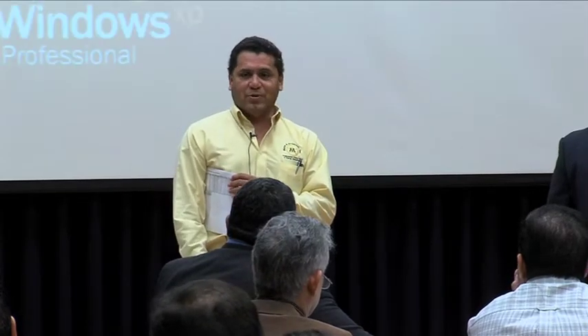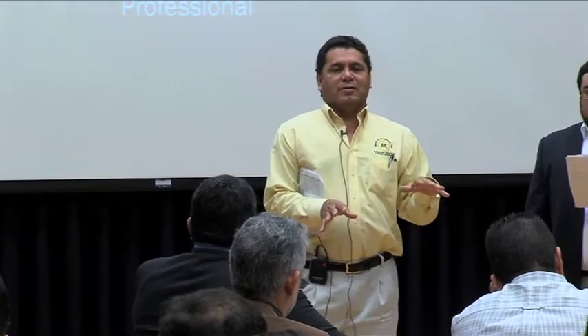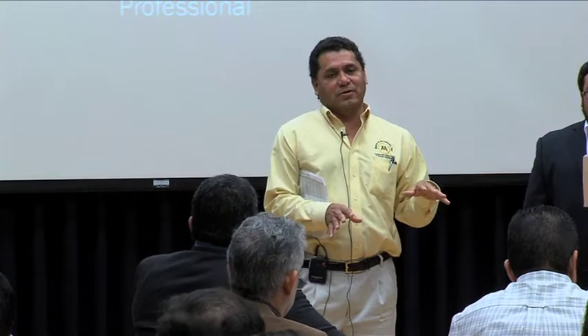There's heat recovery chillers, and if you want to get into that, Perry is the guy to talk to. I did them when I was with AEP. I put a couple of them in a couple of colleges up north, and they can replace 5 million BTU gas boilers. You're just moving the wasted heat from your cooling tower, where you're evaporating all that water, and you take it and preheat the water, just reversing a chiller. Those technologies are available out there, and that'll keep your demand down. It replaces a lot of stuff out there. So when he talked about it, and that's what I was going to tell you, we go with a water-cooled chiller first, air-cooled chiller second. When you start getting to your smaller systems, if you're not going to put in an air-cooled chiller, then you should start going to heat pumps.